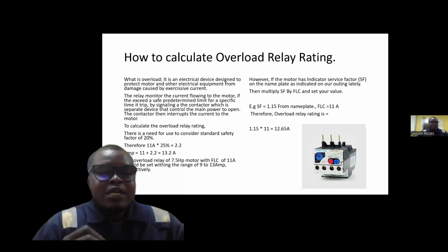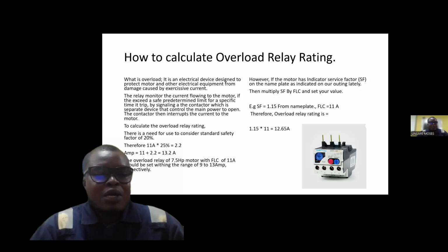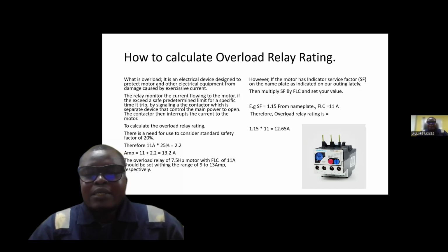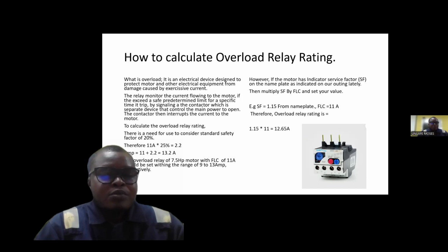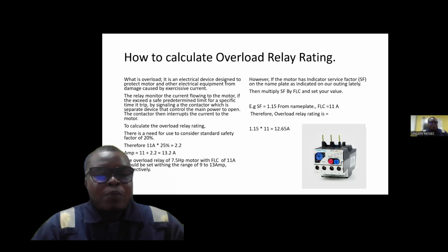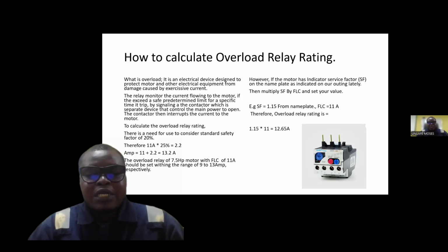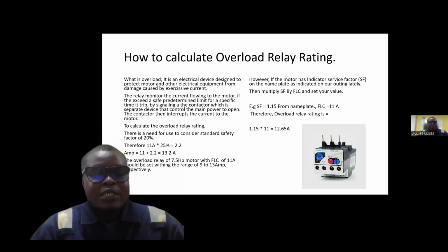To calculate the overload relay rating, there is a need for us to consider the standard safety factor. In this scenario, our standard safety factor is what? 20%. And when you multiply 20% as it is on the slide, we have what? 2.2. So when you add 2.2 to 11 amps, which is the full load current, it is going to give you what? 13.2 amps. Now, our overload relay for the 7.5 horsepower motor is rated to be what? 13.2 amps. Now, when setting this overload relay, you set it within the range of 9 to 13 amps.